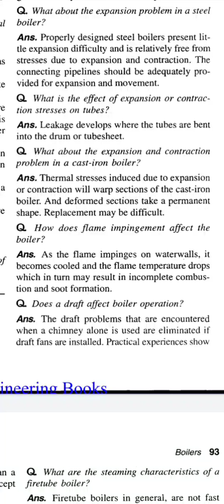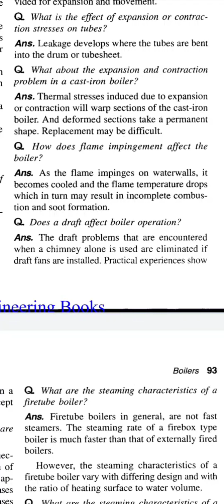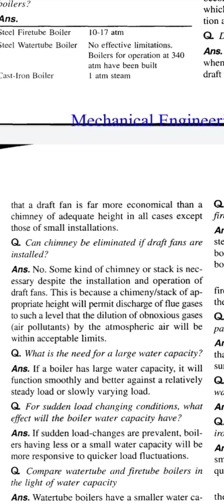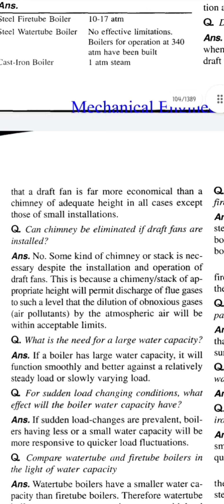Question: does a draft affect boiler operation? Answer: the draft problems that are encountered when a chimney alone is used are eliminated if draft fans are installed. Practical experience shows that a draft fan is far more economical than a chimney of adequate height in all cases except those of small installations.